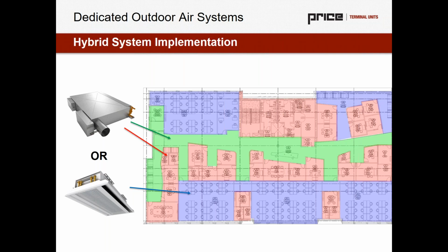Now, one thing I was going to point out: if we take Mark's advice and look at those sensible fan powered terminals in the perimeter, in the purplish periwinkle blue color there, they like to see that lower internal pressure drop. If we push the chilled beams on the interior, that's essentially pressure drop that we have to get to the exterior, so it's almost like free additional pressure drop on those chilled beams. So that's an interesting thought process: use the chilled beams on the interior, where they want to see a bit higher pressure. And as we have losses through the ductwork getting to the sensible fan powered terminals, they like to see the lower pressure because the fan picks up the remainder. So that's how I would address that one. Let me know if that answers the question, Glenn.